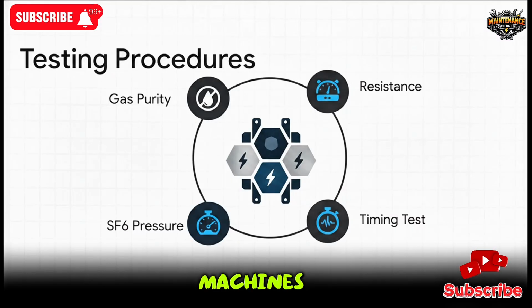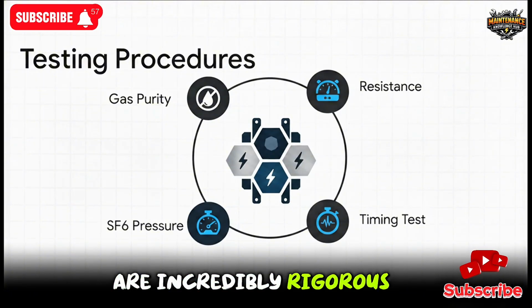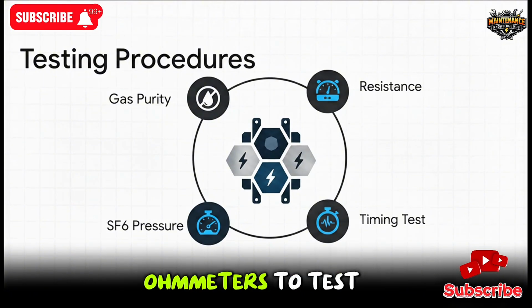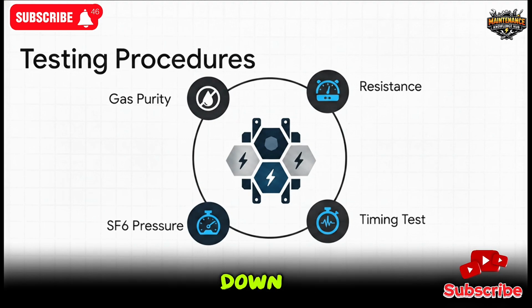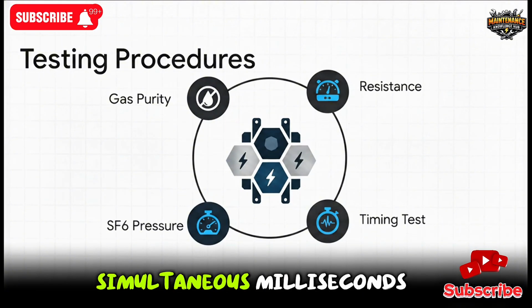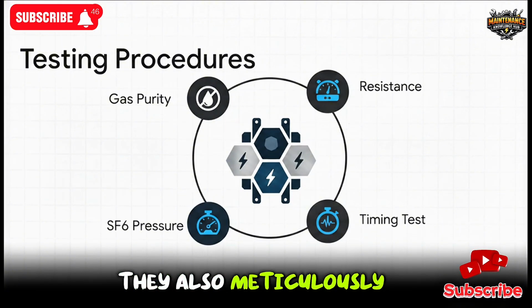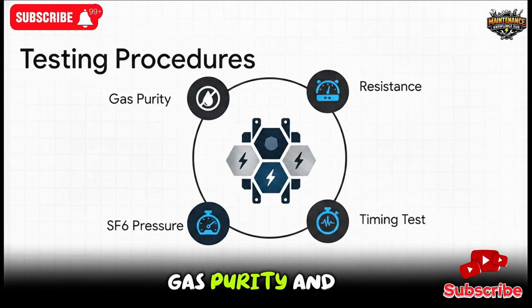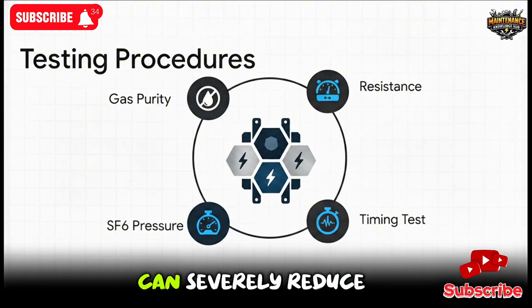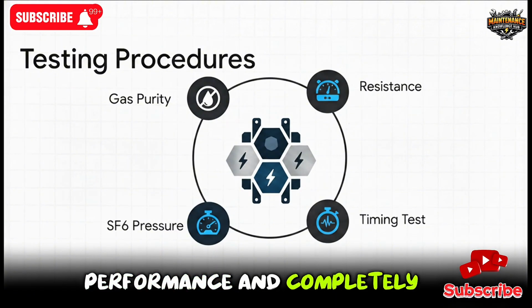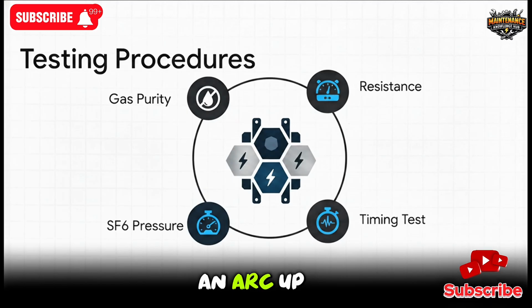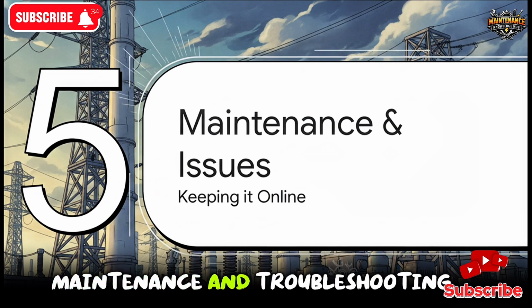Now, because these machines literally act as our grid's last line of defense, the testing procedures are incredibly rigorous. Technicians use highly sensitive micro-ohm meters to test contact resistance, making absolutely sure those massive contacts aren't wearing down. They use circuit breaker analyzers for timing tests, verifying that the contacts open in exact simultaneous milliseconds. They also meticulously check the SF₆ gas pressure, gas purity, and especially the gas moisture. Listen, even a tiny, microscopic amount of moisture can severely reduce the dielectric performance and completely ruin the breaker's ability to stop an arc.